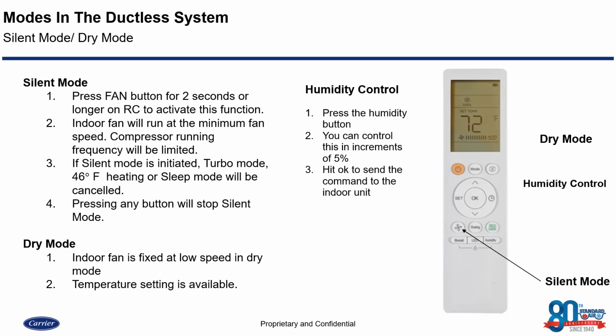The compressor will be running at a very limited frequency or very limited speed, which means if they decide to do this when we're in peak load conditions, let's just say middle of July, beginning of August, when we're experiencing 90, 95 degree outside air temperature consistently, when you turn down the speed of the indoor fan, the outdoor fan, and the compressor, you limit capacity. So while the system may be silent or quiet as to not disturb somebody, you're also limiting the capacity the system can deliver, especially on those peak times of year. Now, if that silent mode is initiated, turbo mode, 46-degree heating where that setback, or the sleep mode will be canceled. And in order to exit the silent mode, you can press any button and that will get you out of your silent mode on the wireless remote controller.